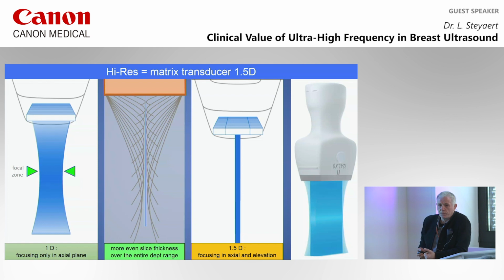And this is very important because an ultrasound image is not just a virtual slice, it has a certain thickness, it has a certain shape. In a normal linear transducer you have a shape like this. It's always the thinnest slice at the level of the focal point. But with these several rows of crystals you can focalize in different directions, not only in the plane of the image, but also in the elevational plane. So you can have a very fine slice with a very even thickness from top to bottom.